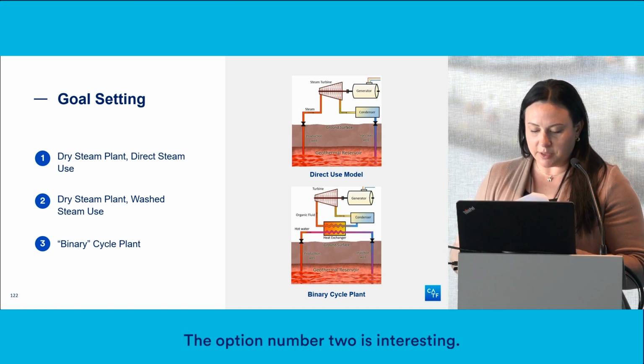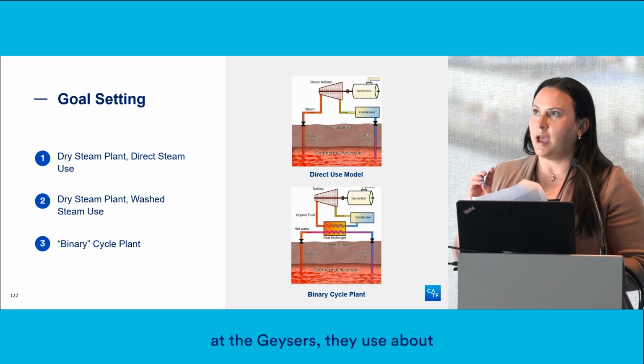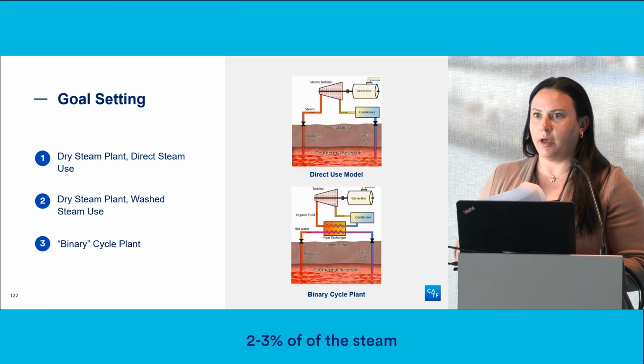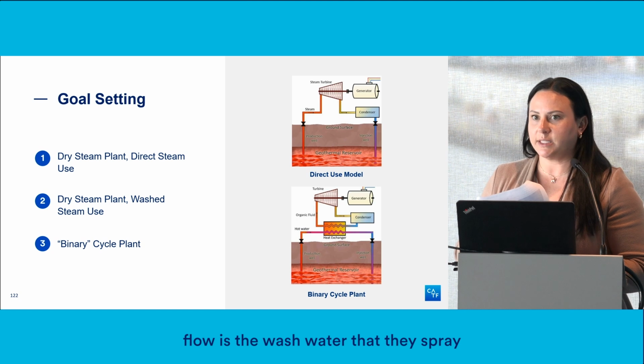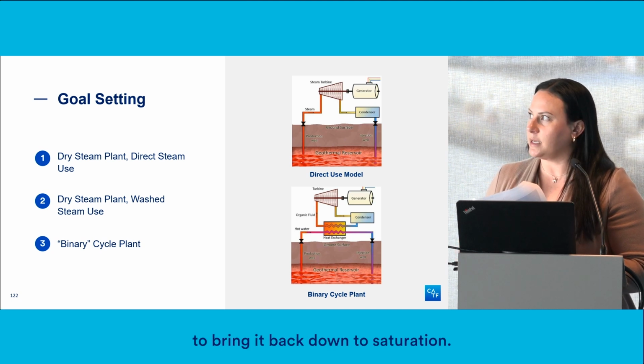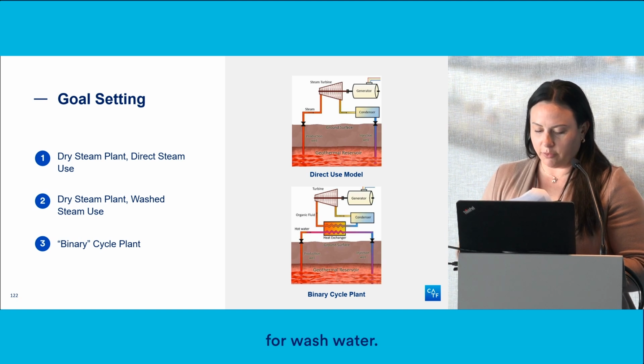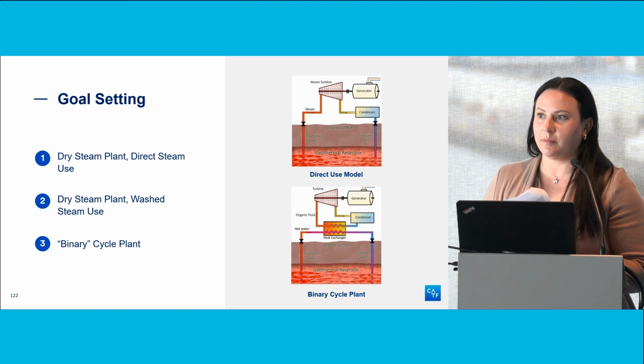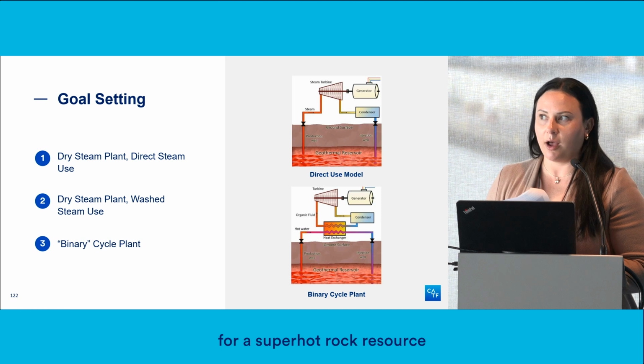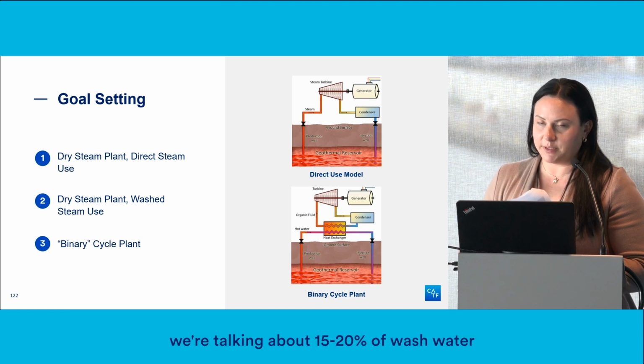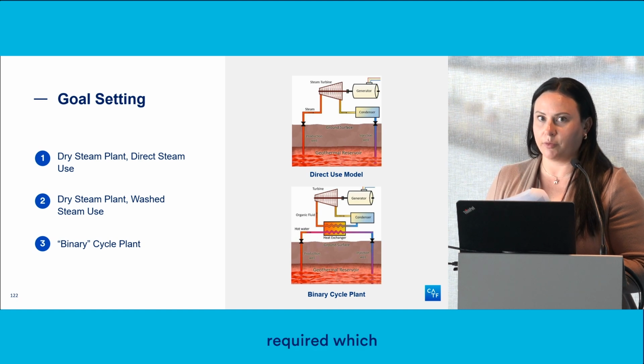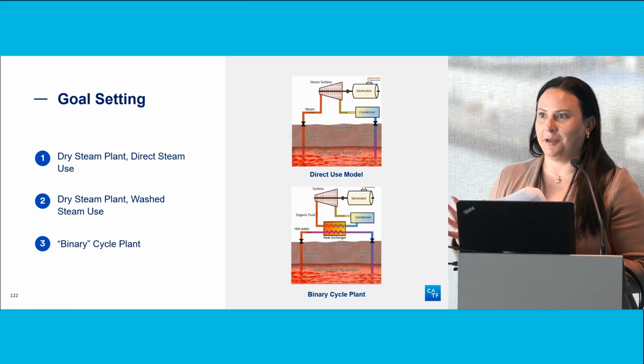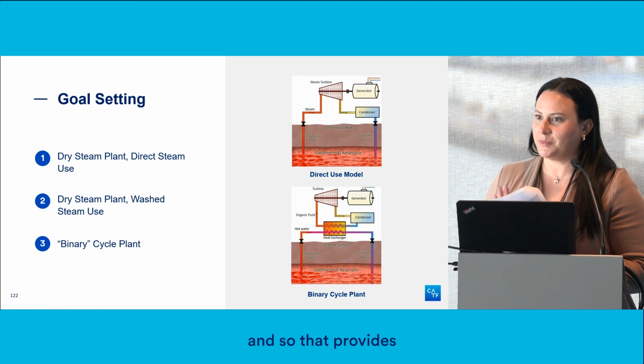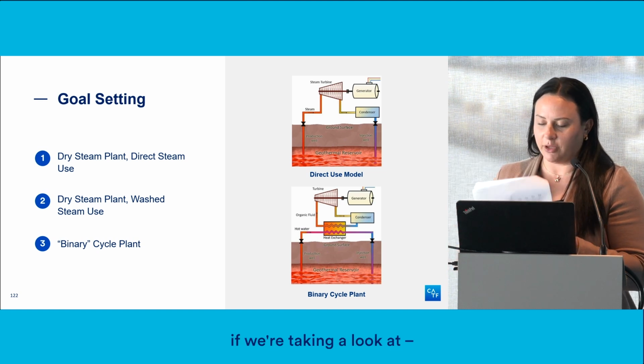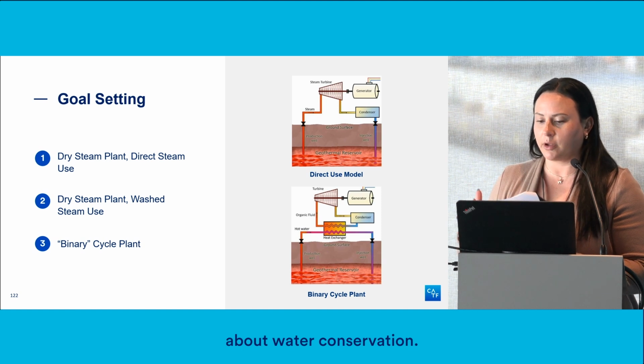The option number 2 is interesting. At the geysers, they use about 2 to 3% of the steam flow as wash water, sprayed on the steam upstream of the turbine to bring it back down to saturation. For superheated steam at the temperature and pressure for a super hot rock resource, we're talking about 15 to 20% wash water required, which is a huge jump. As we know, water is a sacred resource, so that provides some issues if we're concerned about water conservation.